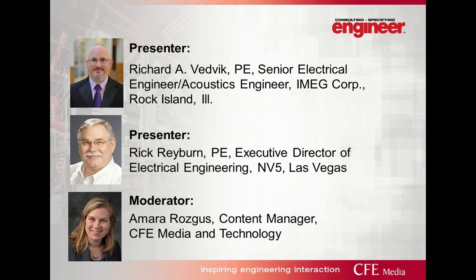And I could do an entire hour just talking about 3-pole versus 4-pole and applications, and we could get into the details on that. But what you're always going to take into consideration, we see a lot of 3-pole switches with solid neutrals in Y configurations. Now, if there isn't a neutral being used, for example, it's a motor control center, it's 3-phase motors only, and you don't have a neutral, then having a 3-pole without a neutral load on there is fine.